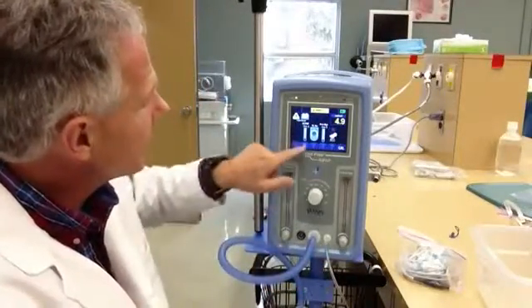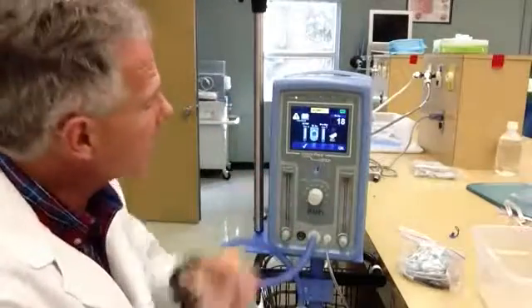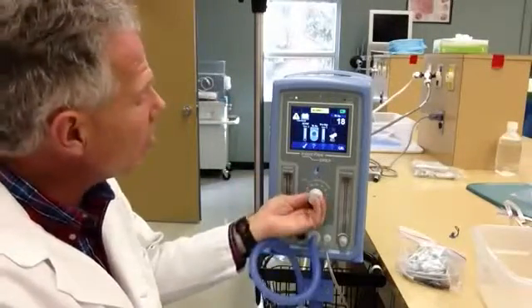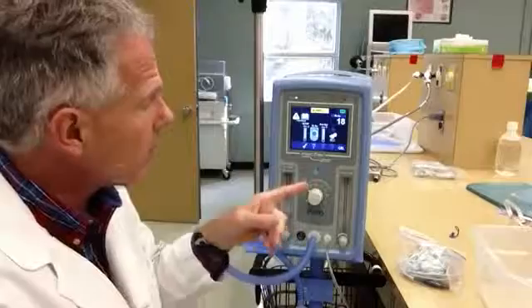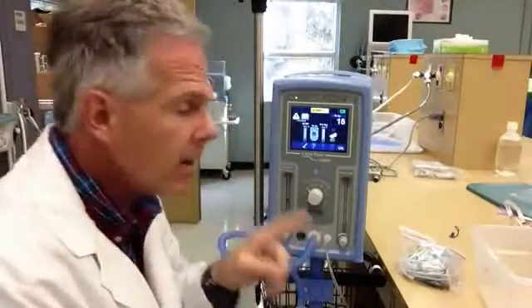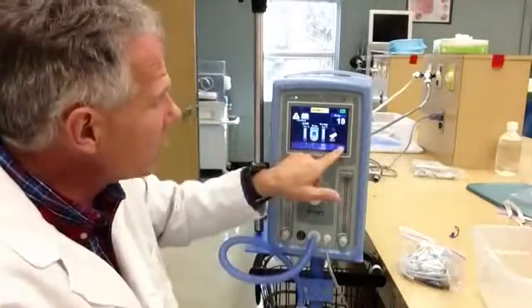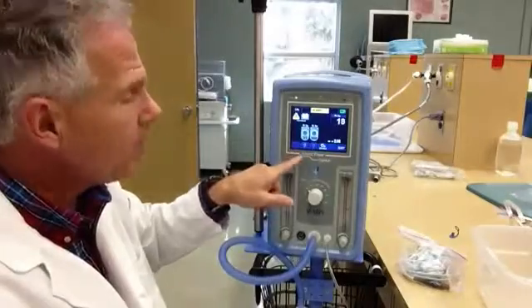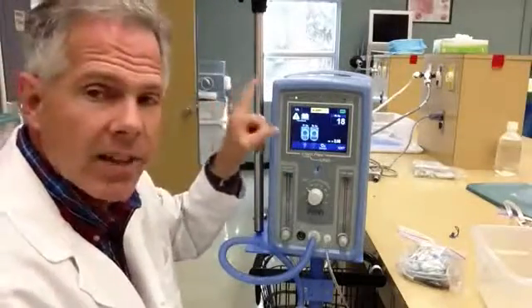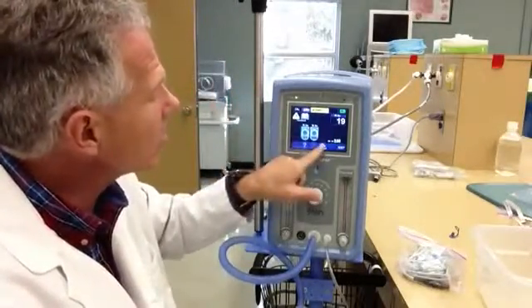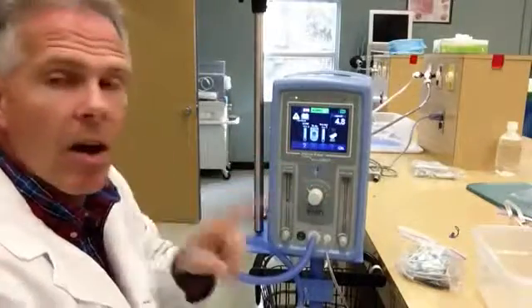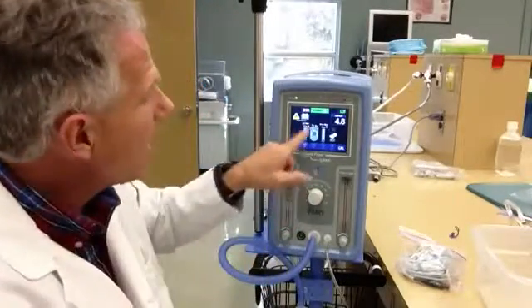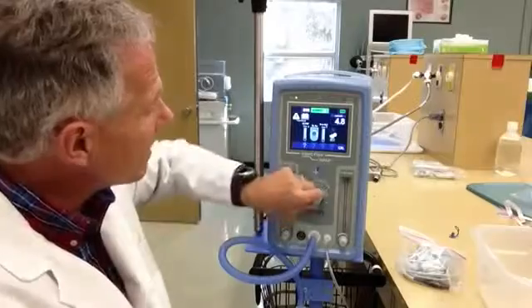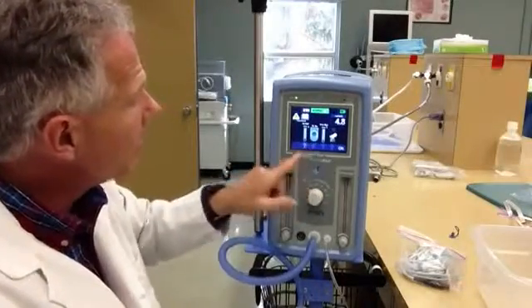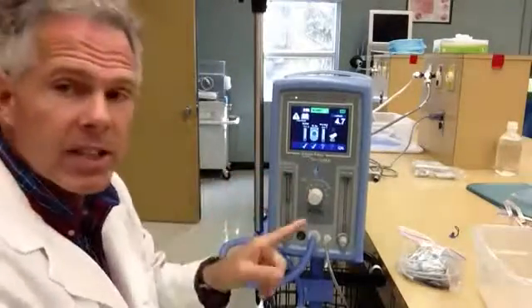So I'm going to just touch this. Okay, it's past that. Now it's asking, make sure you set the FiO2 appropriately for your patient. Now I can calibrate a built-in oxygen analyzer just by hitting this cal button in here, but we don't actually have this ventilator hooked up to oxygen right now. So I'm just going to disable the oxygen analyzer component. But it does say, do I want to have it set at the correct FiO2 for my patient? So I'm going to hit yes for that.